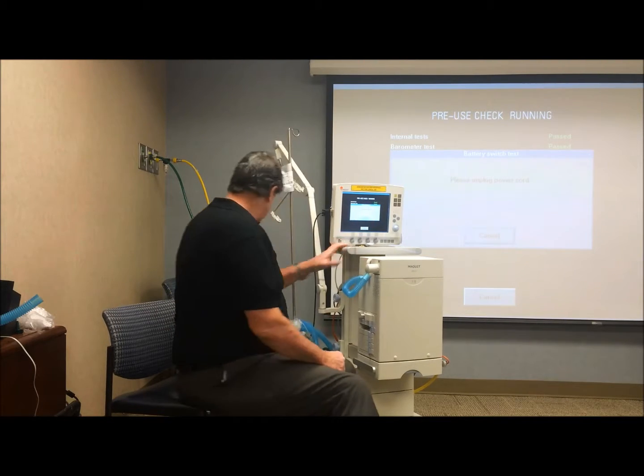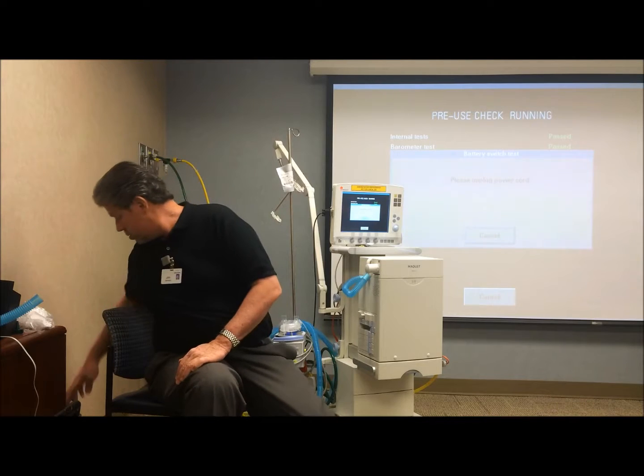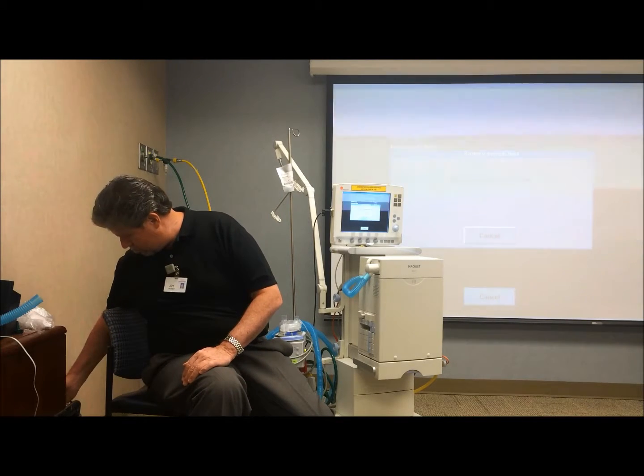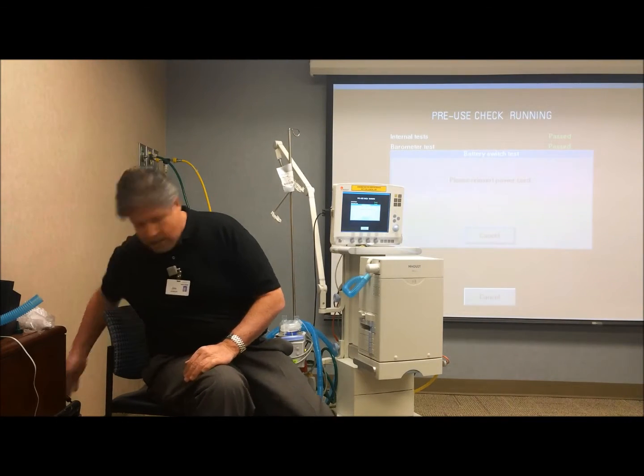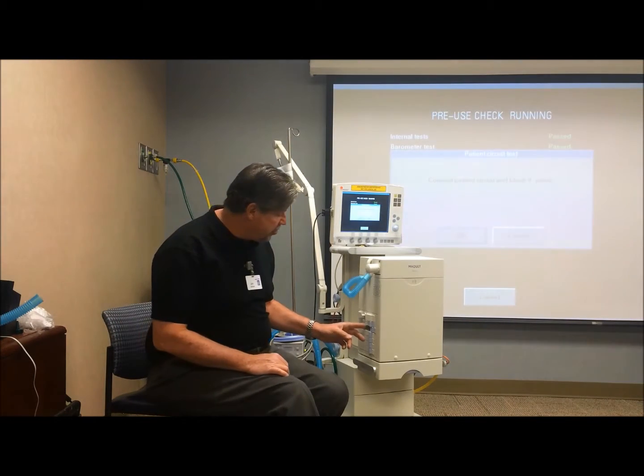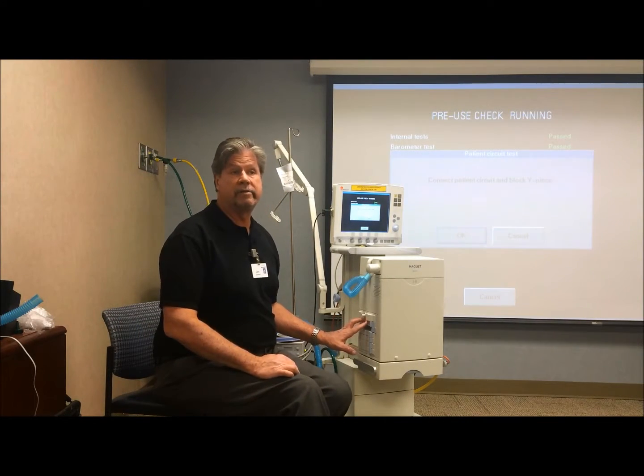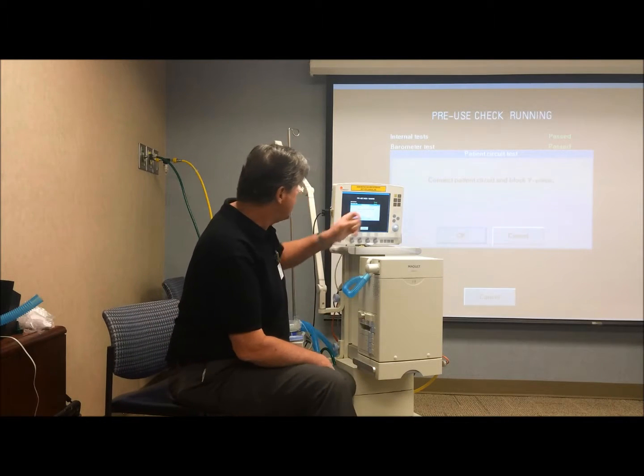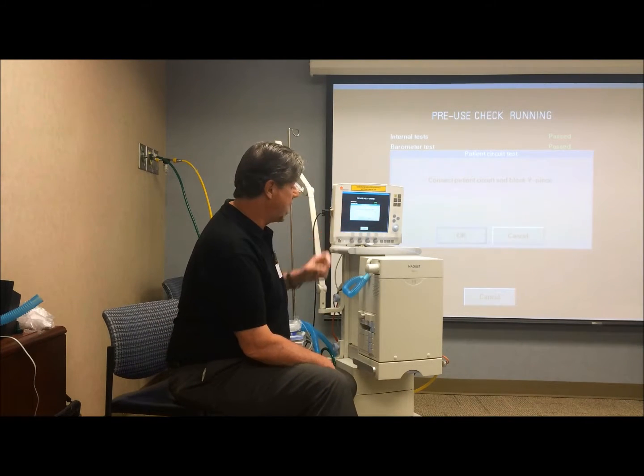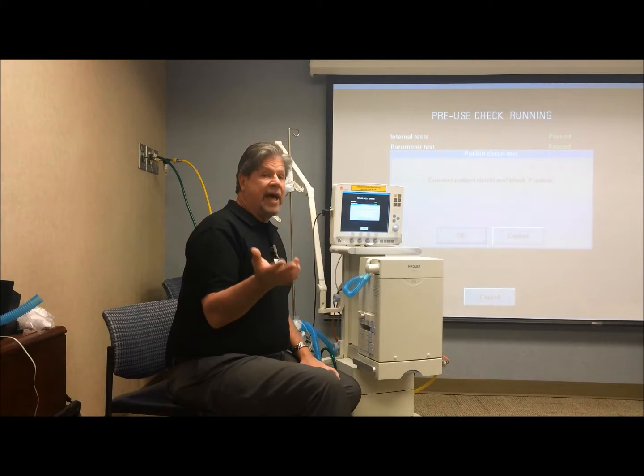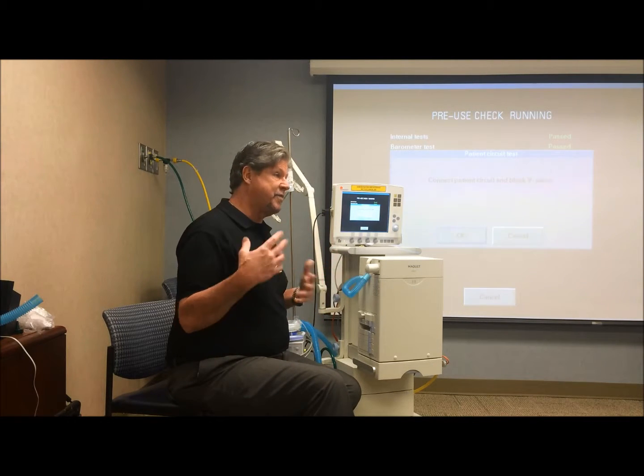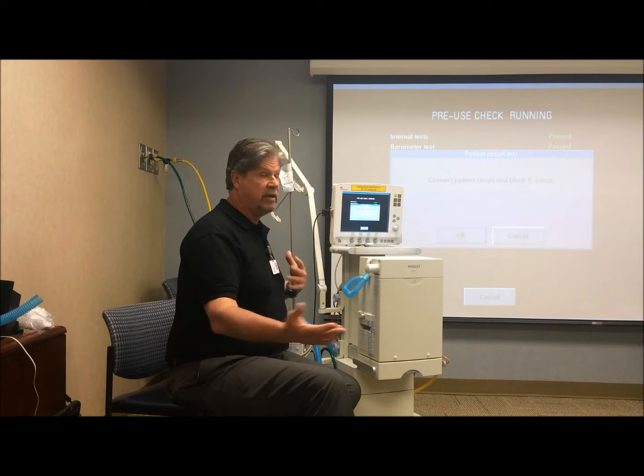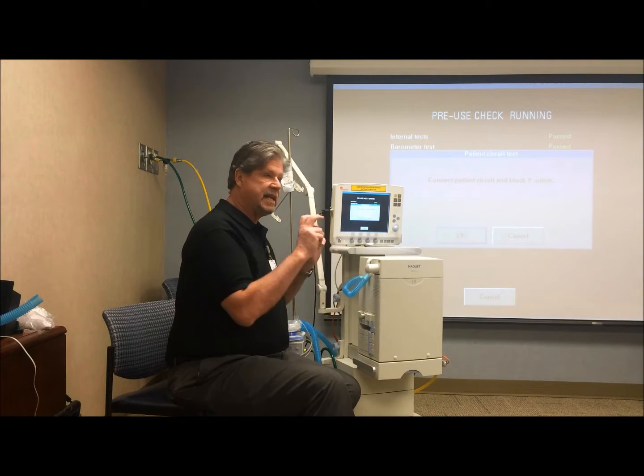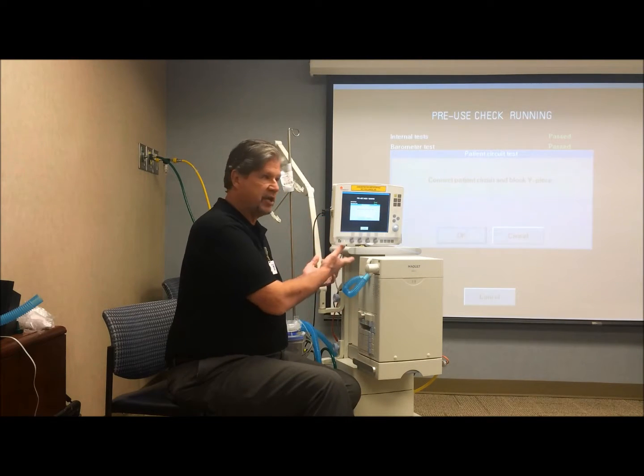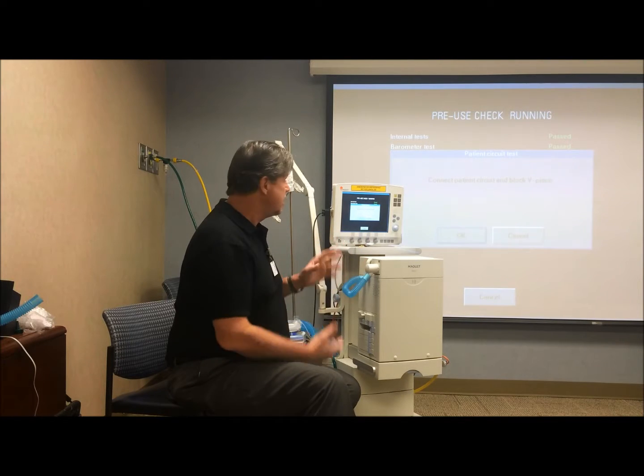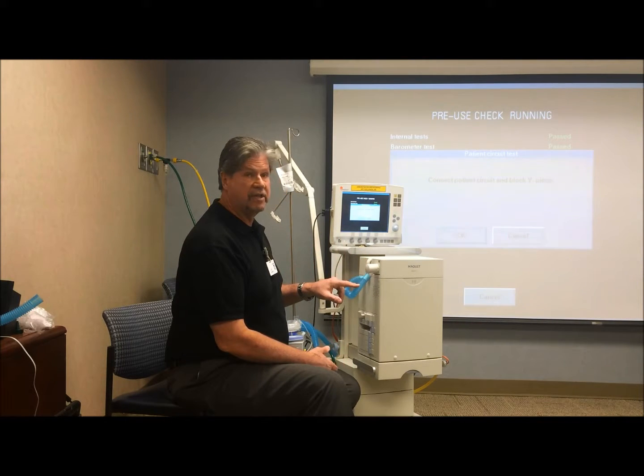So now it says unplug the power cord. And plug it back in again, and when you do that, what it's doing is testing the batteries, to make sure the switching mechanism is all right. So now it says connect the patient circuit and block the Y. I would imagine that you've all learned this, because what you're telling me is you don't put a circuit on the ventilator. You probably leave this on as the patient circuit, because all you're doing is testing the integrity of the ventilator. So we'll do the same thing, we'll just leave this on here.